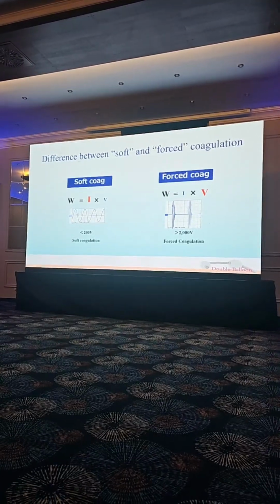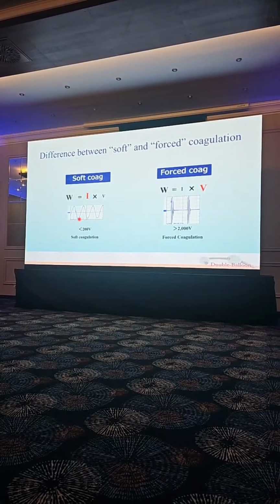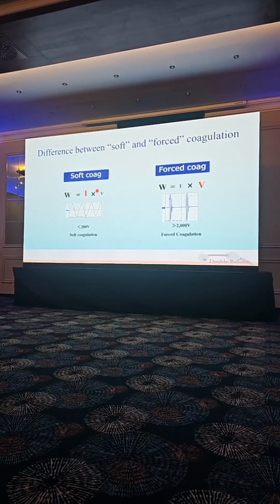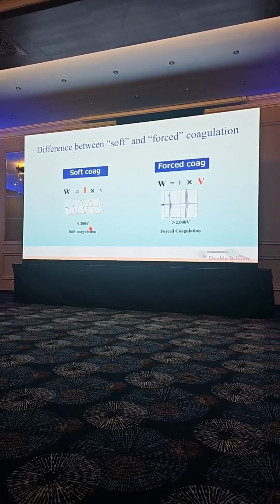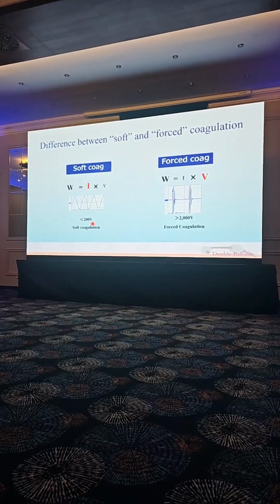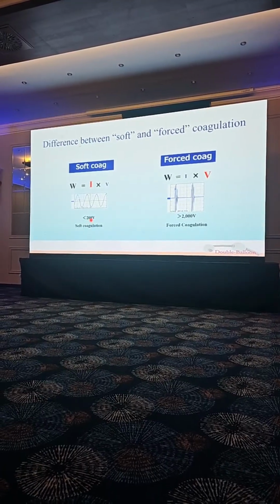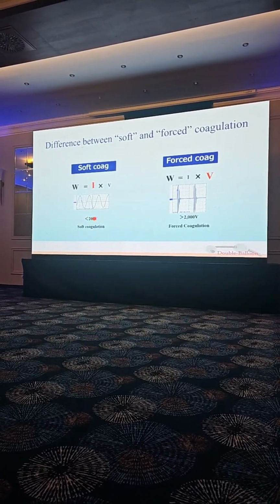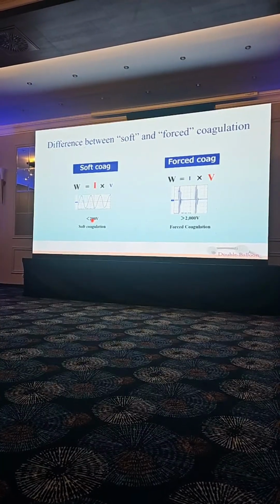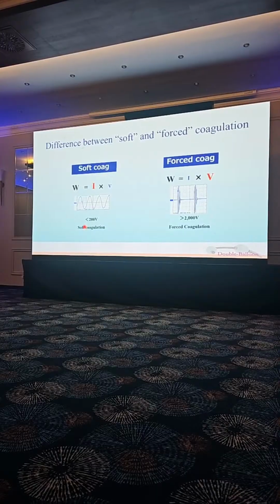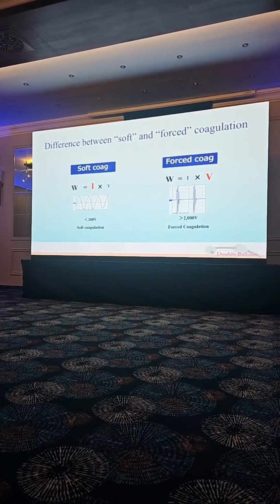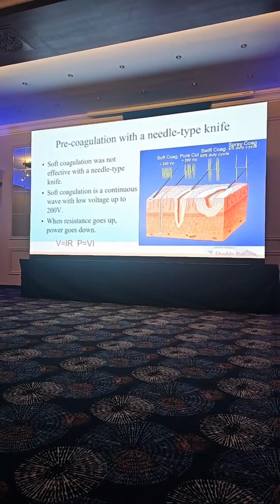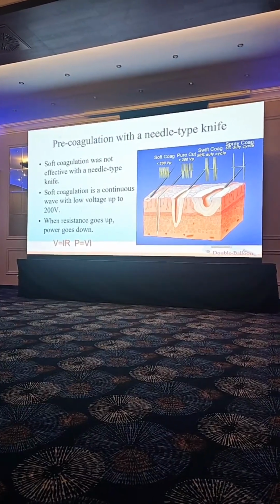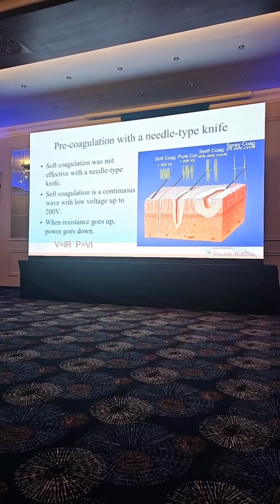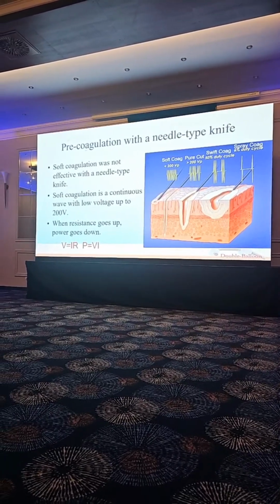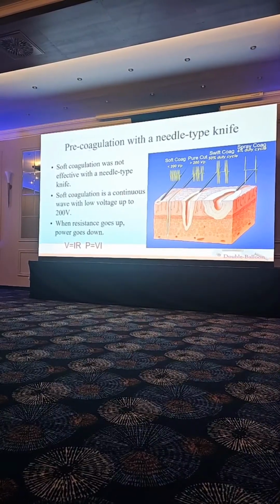But for soft coagulation, the wave shape is the same as the cutting current. But cutting requires spark, and at least more than 200 volts are required. So if you decrease the voltage to less than 200, then it doesn't cut anymore. That is the soft coagulation. So soft coagulation is very good for the hemostatic forceps. Then why didn't I use soft coagulation with a knife? That's because it didn't work. Why didn't it work?